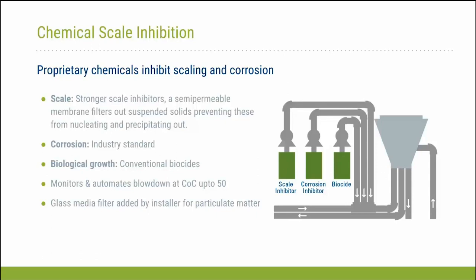Yeah, so in a normal cooling tower water treatment system, the three primary chemicals that are used for water treatment are a scale inhibitor, a corrosion inhibitor, and then a biocide. And normally the rate limiting factor for the cycles of concentration that the system is going to be operating at is the effectiveness of the scale inhibitor.